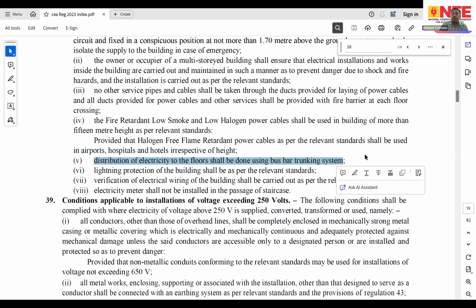And again, when it comes to high-rise towers these days, bus risers are a very simple practice which simplifies things. Today, we have in Mumbai most of the towers beyond 15, 20 floors, going to a height of almost 50 meters and above. The earlier practice was having all metering boxes at the ground floor or in some dedicated room and then taking all the cables up to the flat.